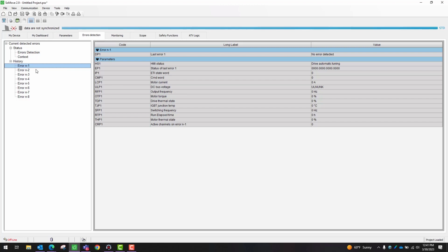Now, what you can do here, once you have all these faults, is click on each fault that's occurred and see a few conditions during the time of the fault. This is especially helpful to know if the faults are happening in a certain pattern, whether your motor is running, whether you're experiencing high voltage issues in the bus due to power quality issues, or if you're having current draw issues. It will tell you what the motor current draw is like, along with your motor frequency.